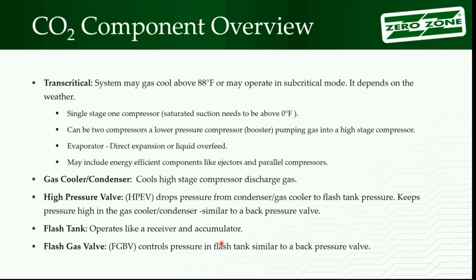receiver and an accumulator. So the bottom half of the vessel is going to be receiver. I get that going through the valve, I've got a mix of gas and liquid. It drops into the receiver. The bottom of the receiver, we're going to fill it with liquid just like any other receiver. On the top side, we've got all that gas. I've got to process it. I've got to do something with it. Now it's acting a little bit more like an accumulator. I want the gas to come out of the tank, but I don't want the liquid to come with it. I want the liquid to stay in the bottom. I want the gas because compressors like dry gas. They don't want a lot of liquid.